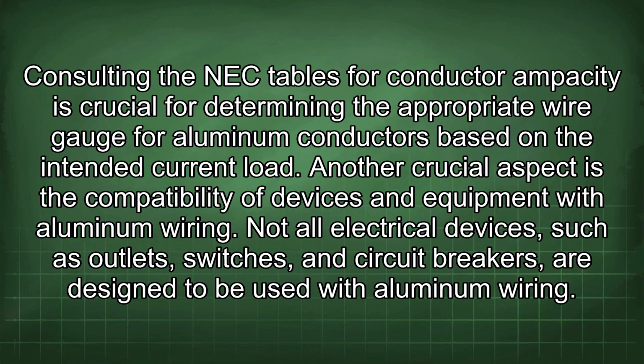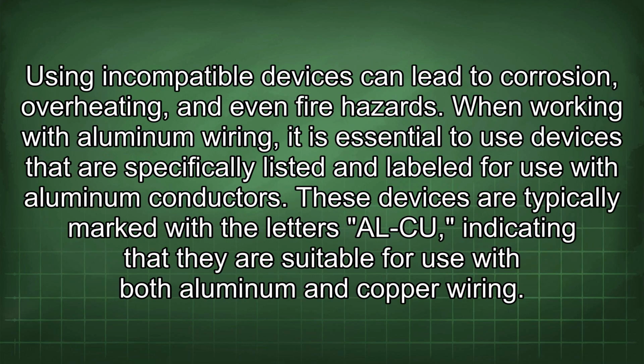Not all electrical devices, such as outlets, switches, and circuit breakers, are designed to be used with aluminum wiring. Using incompatible devices can lead to corrosion, overheating, and even fire hazards. When working with aluminum wiring, it is essential to use devices that are specifically listed and labeled for use with aluminum conductors.